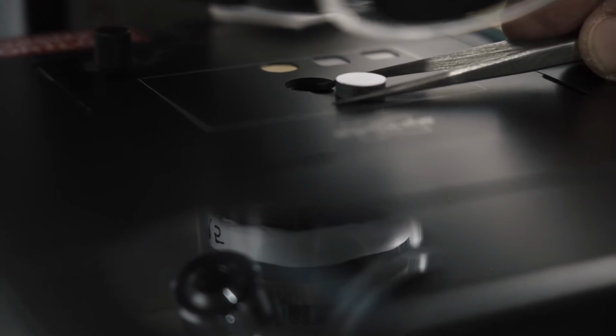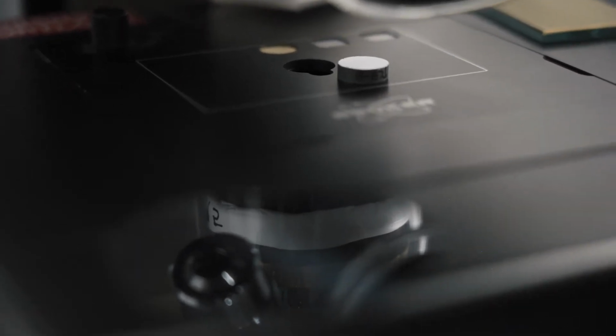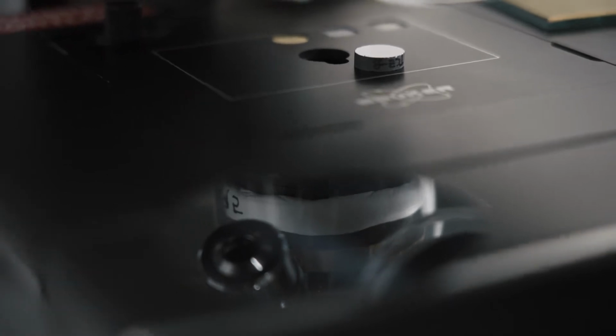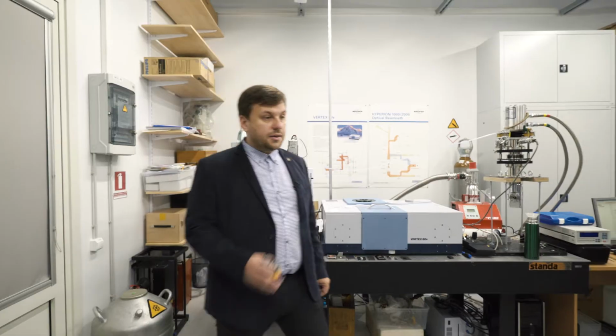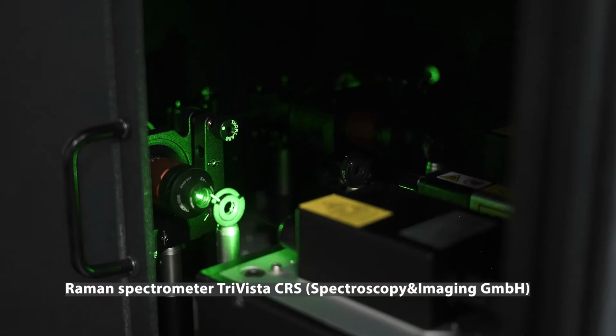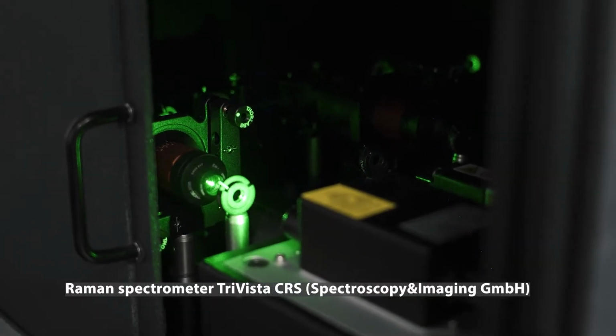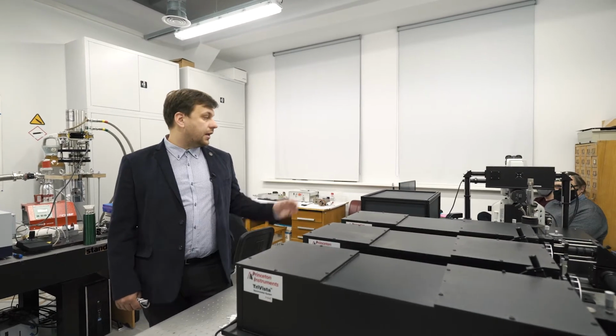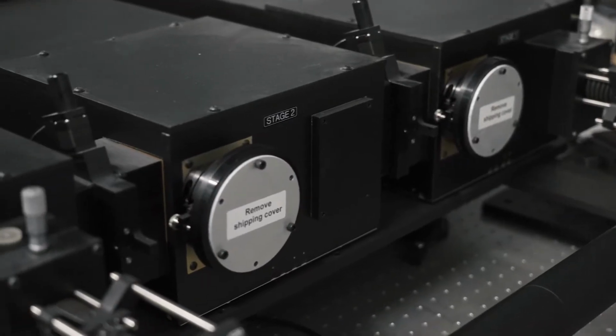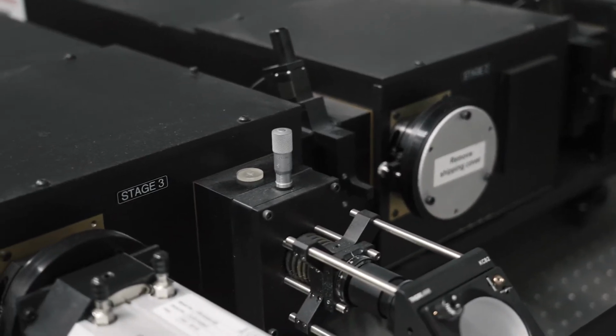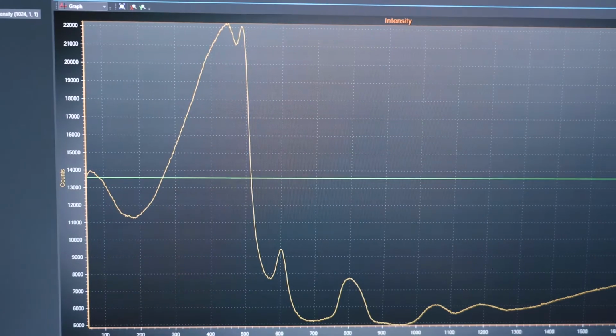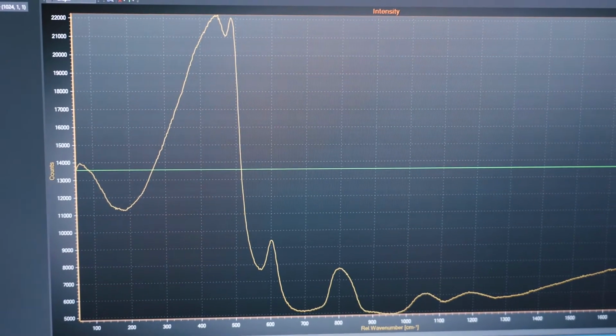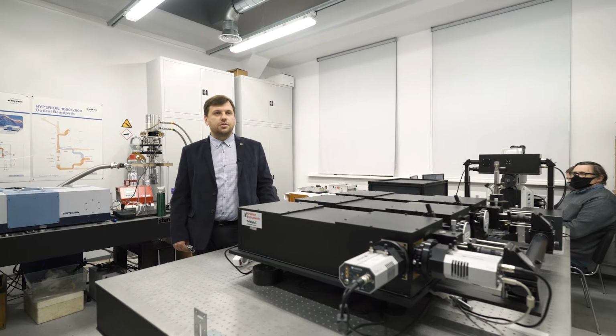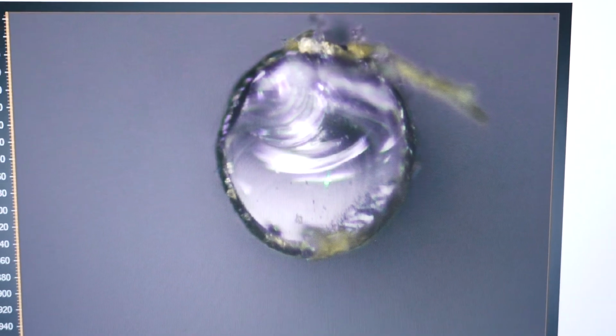This spectrometer is used for academic purposes as well as industrial partners, namely, it is used for detection of ultra-low concentration of impurities in semiconductors by a local company producing solar-grade silicon. The other equipment, also present here in this laboratory, is a Raman spectrometer. It is a confocal Raman spectrometer equipped with a confocal microscope, 3 lasers, and 3 monochromators, thus ensuring excellent signal-to-noise ratio, sensitivity and resolution. It is also broadly used by different laboratories at the Institute for material characterization, as well as 2 local companies producing optical fibers for the characterization of their products.